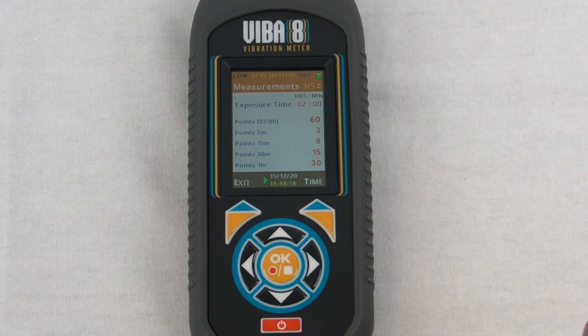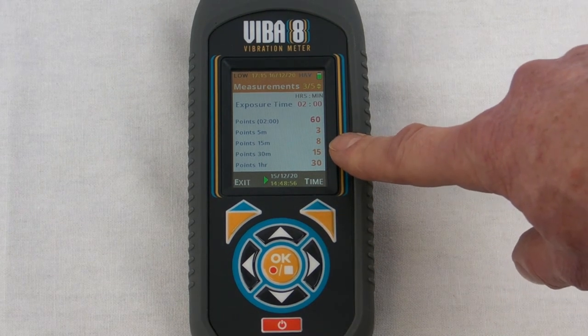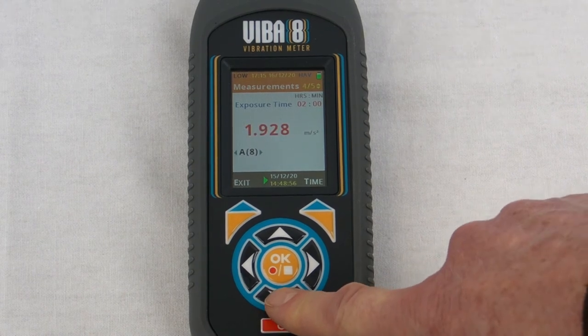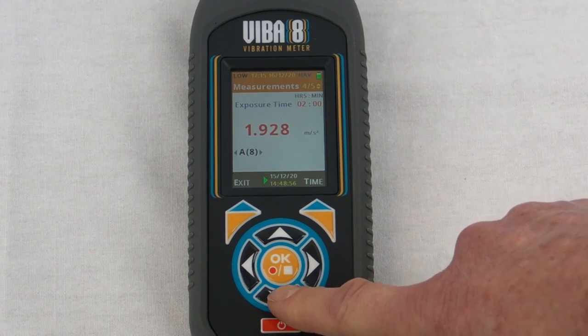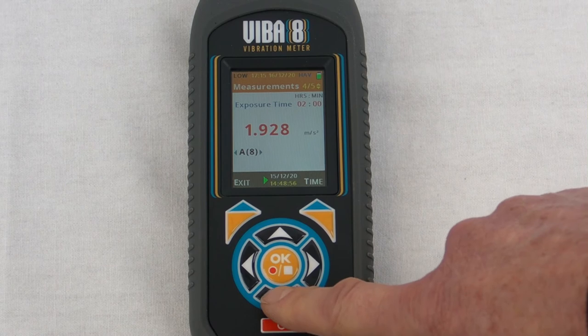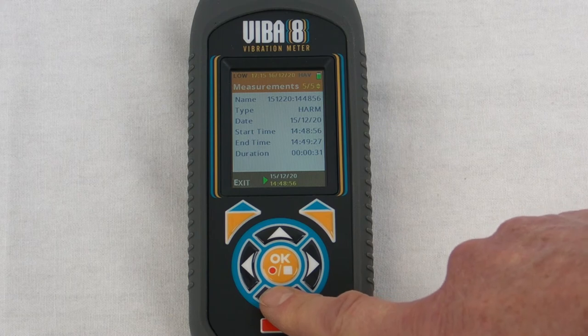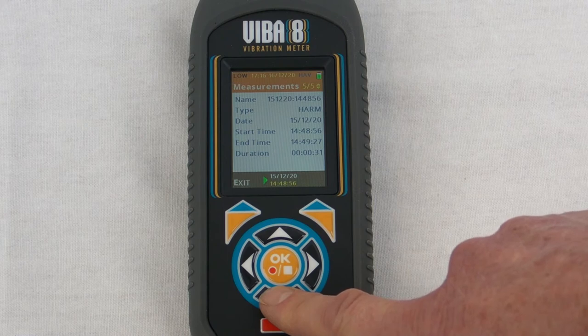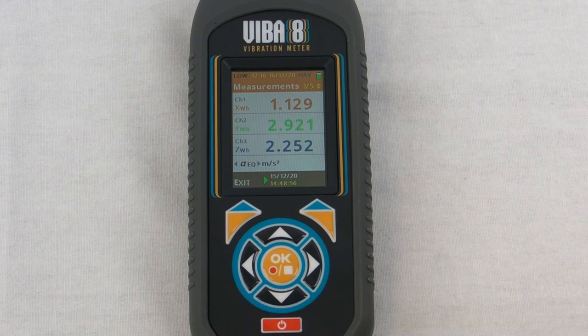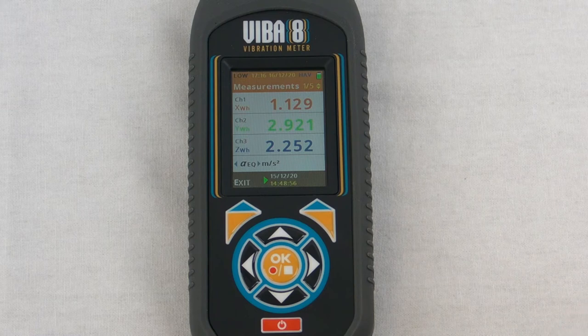The next screen simply has a simple single number display of the a8 value based on the two hour measurements. Following that was just some information about the measurement that was taken, the time and date, what mode it was set in and that kind of information, and then back to the initial screen. So we can see from that measurement we took on the sander sanding that block of wood pointlessly, those are the results that we ended up with.